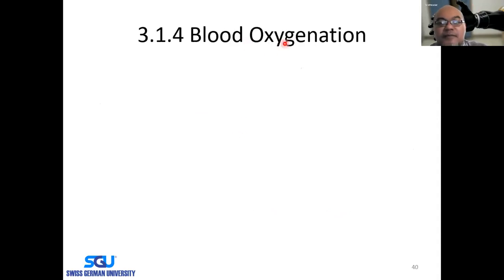Another parameter, unfortunately I haven't made the slide here yet, is the blood oxygenation in the circulatory system. This is the level of oxygen, SpO2. This is quite important now, with COVID-19 and phenomena like happy hypoxia, to measure the content of oxygen. This is usually measured using photoplethysmogram, which measures the relative intensity between red wavelength absorption and infrared wavelength absorption.